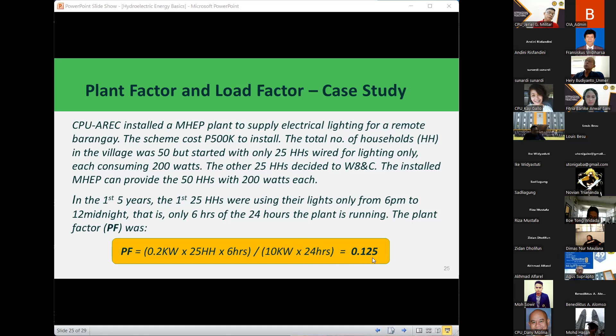So the plant factor was: 200 watts, or 0.2 kilowatt, times 25 households, times 6 hours, divided by the total capacity of the plant, which is 10 kilowatt times 24 hours—that's the total energy generated by the power plant. So the plant factor is only 0.125.